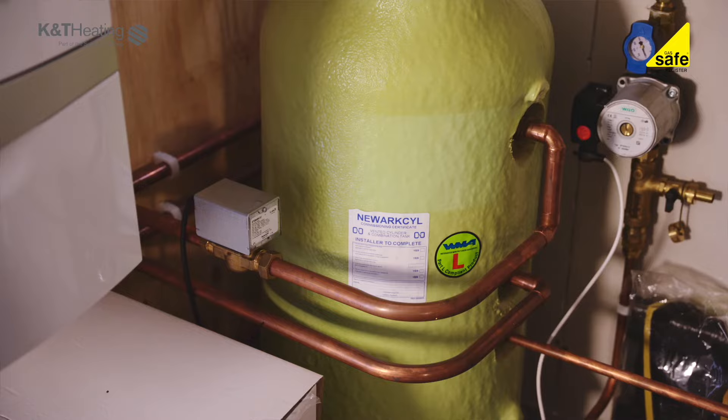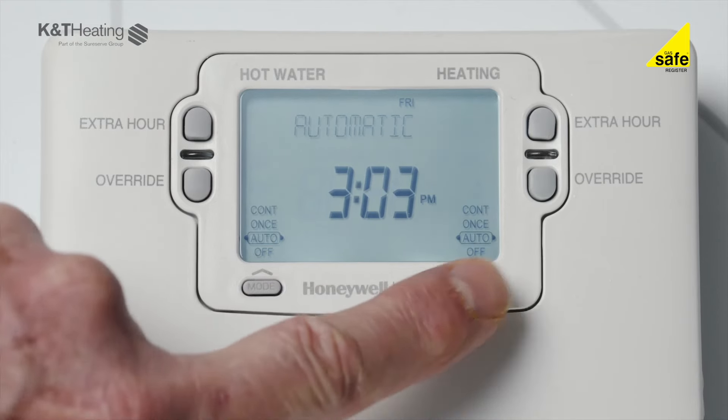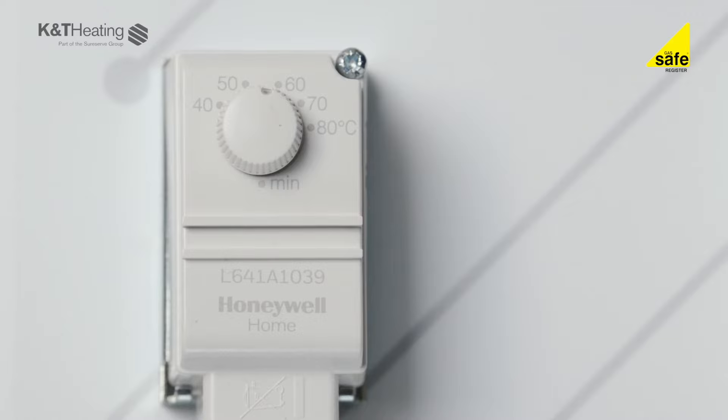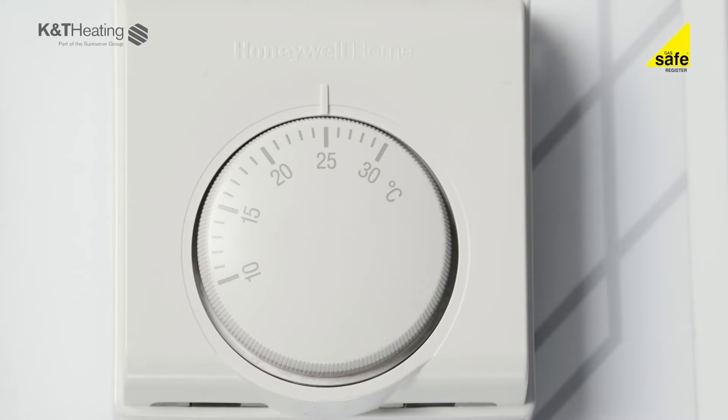A regular or system boiler would normally have a storage cylinder for hot water. Do you have a cylinder fitted in your airing cupboard in your home? If the answer is yes, you have a regular or system boiler. Is your heating working? Please complete the following steps to ensure your boiler is enabled for heating function. Is the boiler control timer set to 24 hours or continuous to enable it to call for heat? You will need to ensure the clock timer is calling for heat to create the demand. Is the boiler heating thermostat turned up to maximum? If the boiler thermostat is set too low, the boiler may not turn on. If you have one, is your room thermostat turned up to call for heat — approximately 25 degrees? The thermostat needs to be set hotter than the space in which it is fitted to create a demand for heat. The room thermostat is normally fitted on the wall in the living space or hallway.